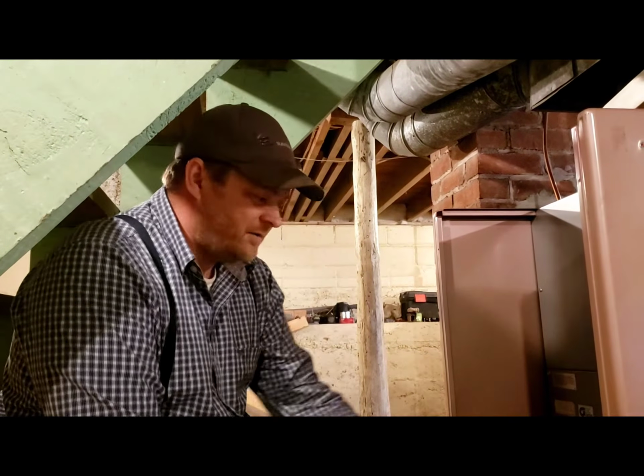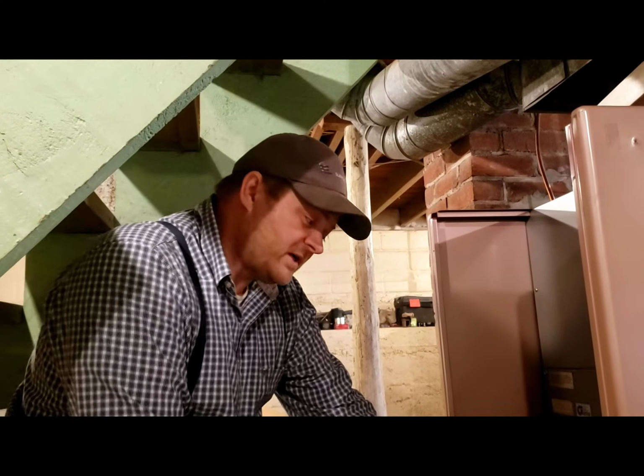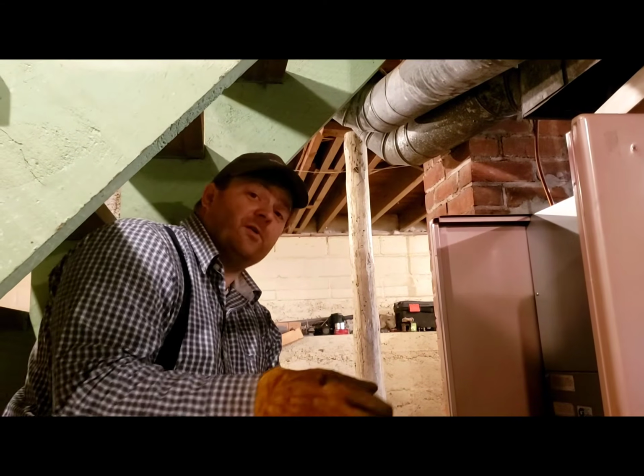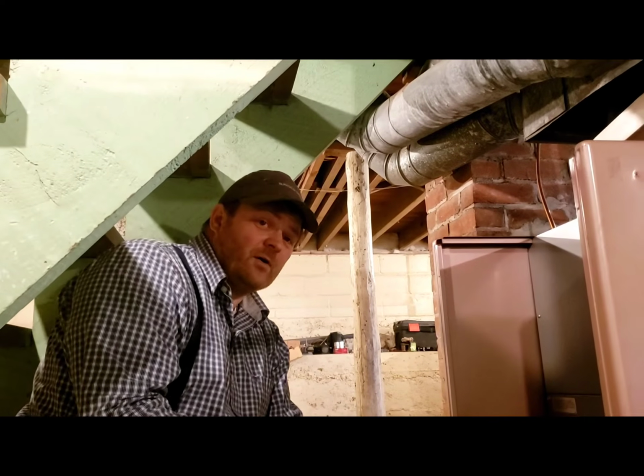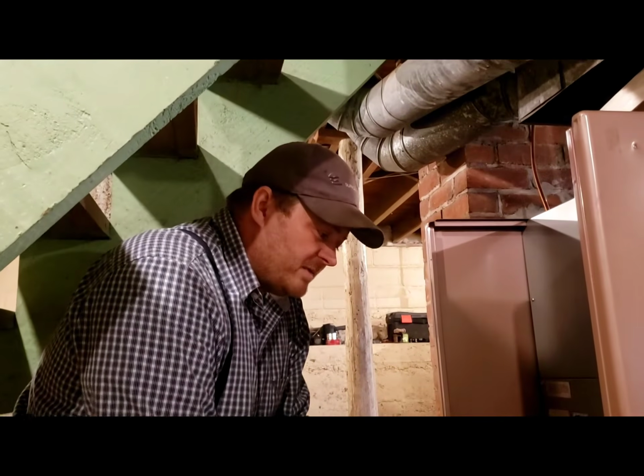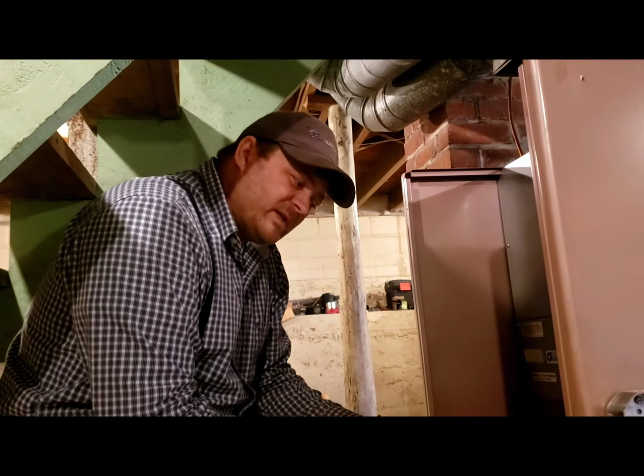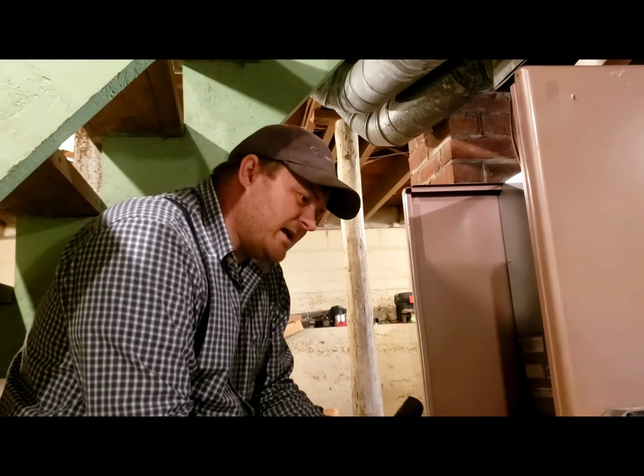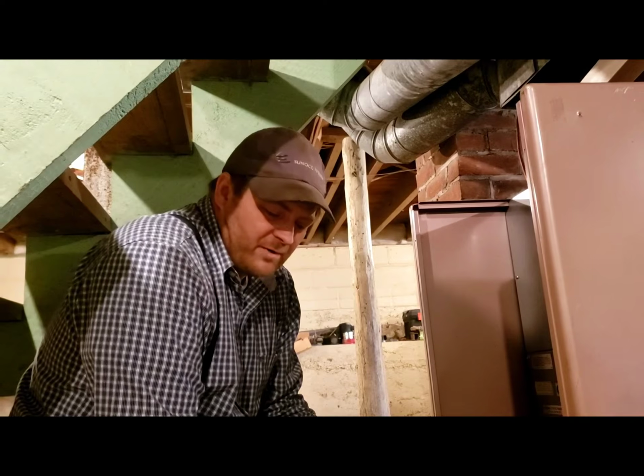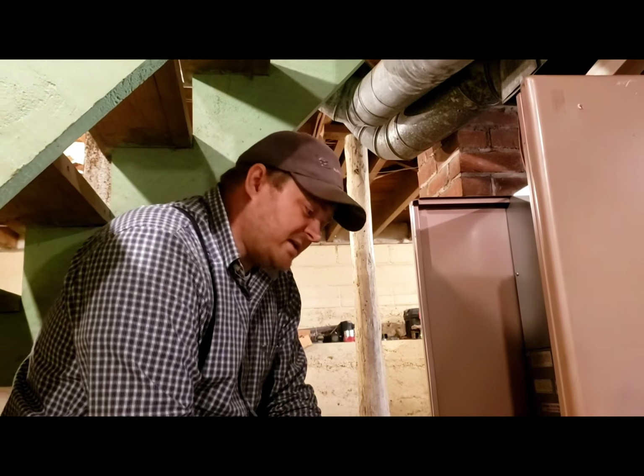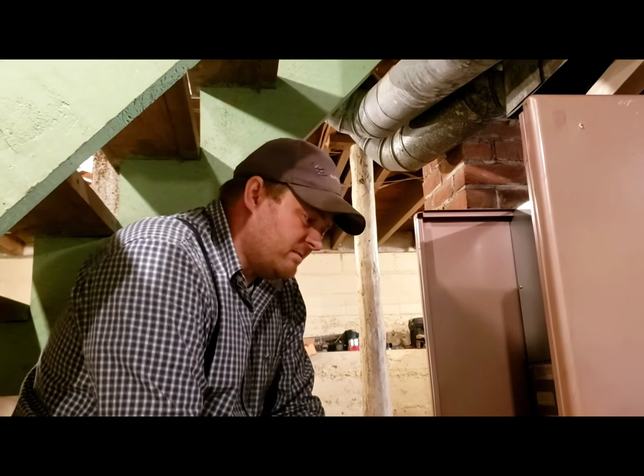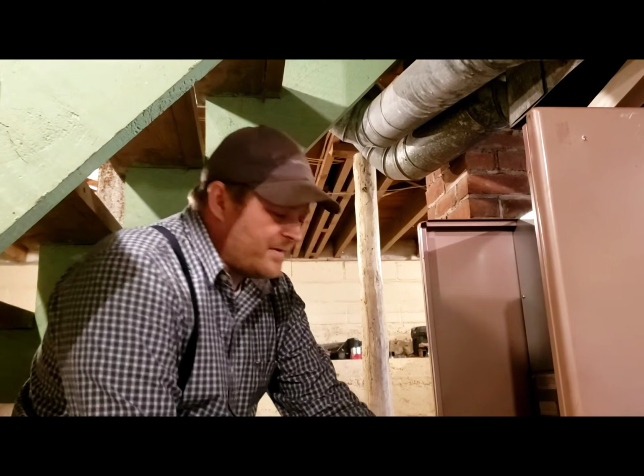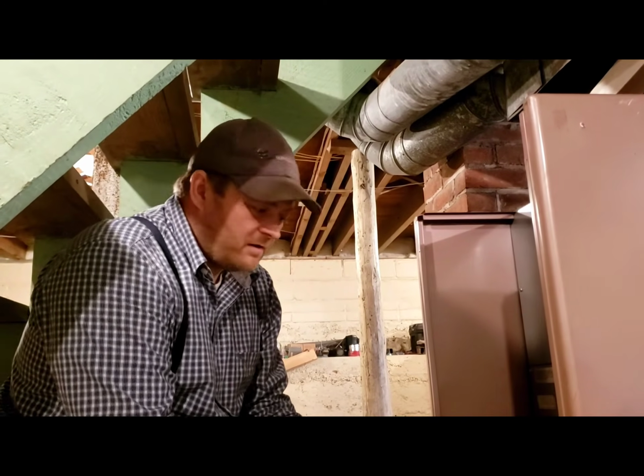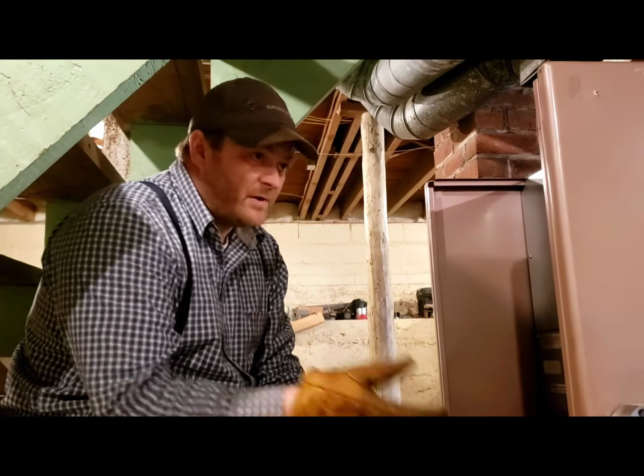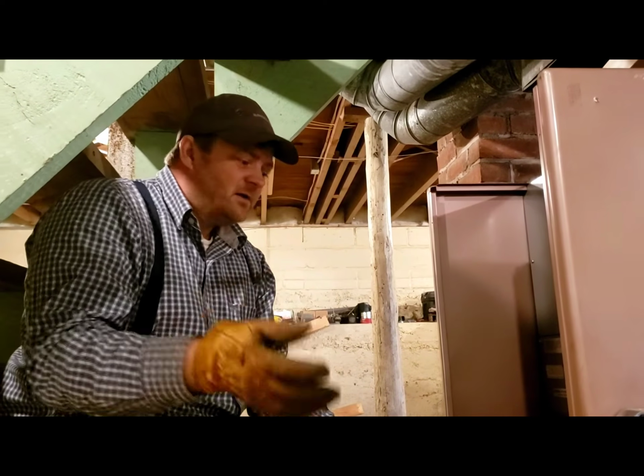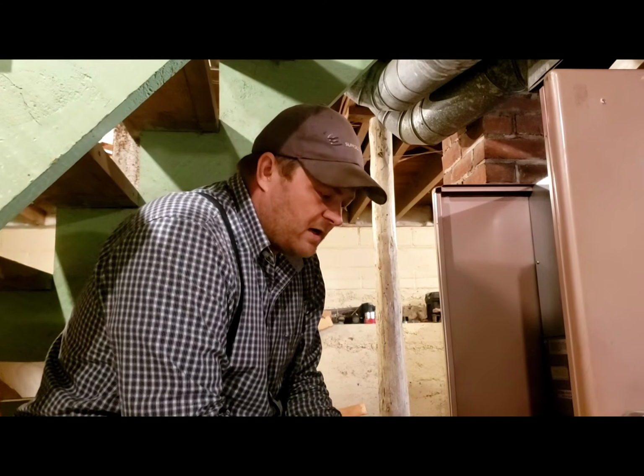They're not checking how strong the transformer is, because a weak transformer might get weak for a year or 2 before it finally dies. Well, that could be caught in the fall or summer. If it's not performing, you can just switch it out. Maybe somebody might not want to pay for that. If somebody said, hey, this is going to fail eventually, but you can't predict when, you can catch that stuff in the summer if the person's willing to pay. If your primary is clicking on and off, it's going to fail. Maybe it's been doing it for 6 months and you don't even know it, and it starts doing that during a checkup, you just switch that.